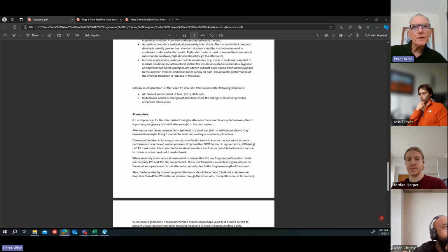Okay, let's have a chat about attenuators. And if you've got any questions, just interrupt me anytime if you want to. If it's impractical or not possible for the internal duct lining to attenuate the sound to acceptable levels, then it's probably necessary to install attenuators in the ductwork system. This will give you much greater attenuation. I know that we do encourage you to look at whether you really need attenuators because they're expensive. But sometimes we have to use them because we can't get the attenuation we need by lining ductwork.